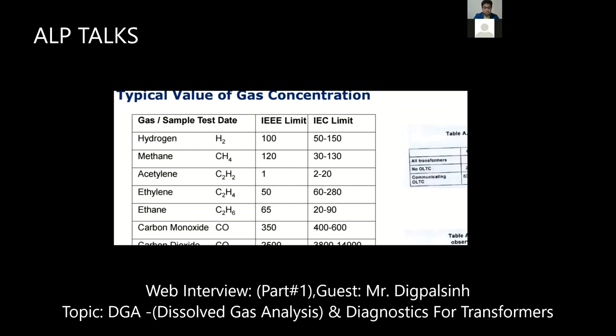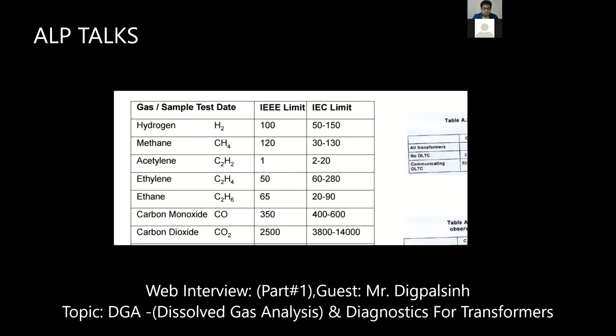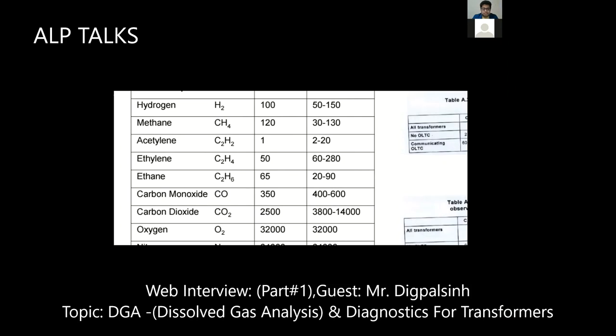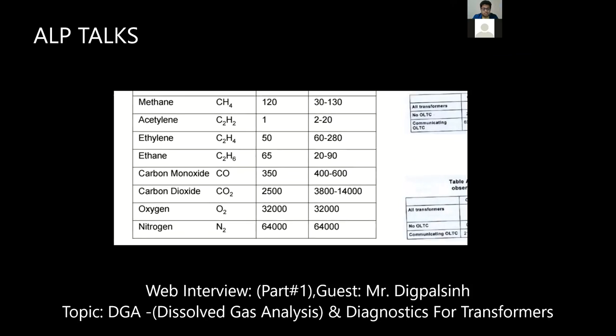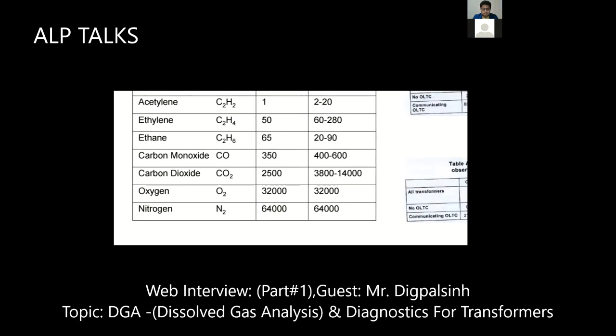Yes. Then ethylene, C2H4. IEEE has given 50 and IEC has given 60 to 280. So for a healthy transformer, the limit should be 50 to 60 ppm, and after 1, 2, or 3 years of use, up to 280, you can say it is normal. There is no need to do any further analysis or shutdown. There is no worry. Okay. Same for ethane: it is 65, and IEC said 20 to 90. Carbon monoxide, 350 ppm. IEC said 400 to 600 ppm. Carbon dioxide is 2,500, and there is again a huge difference. IEC said it should be between 3,800 and 14,000.